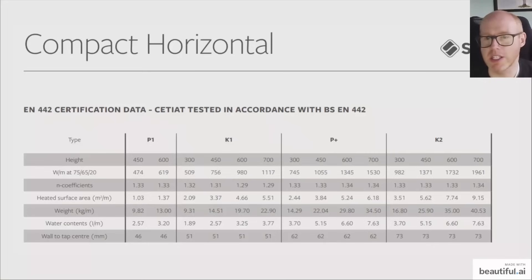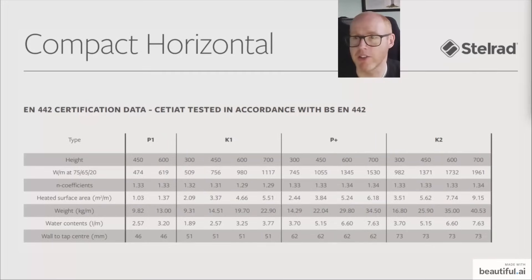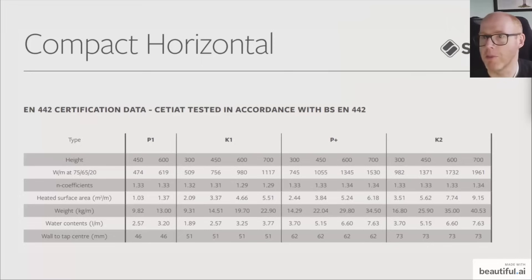This is a little table from Stelrad, a big manufacturer that lots of people will be familiar with. You can look up other charts, but this shows you that per metre of a single panel radiator, or per metre for a two panel radiator, you can see if it's 600 millimetres high, standard height, then it's 6.6 litres of water that goes into a one metre wide by 600 millimetre tall radiator.